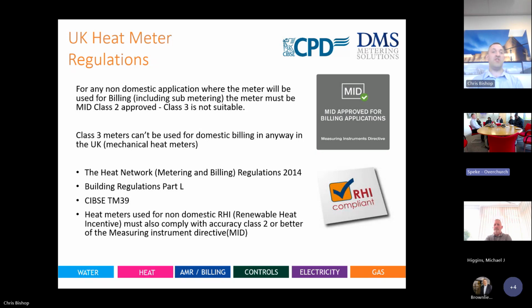Class 3 meters generally were always mechanical. So it was always moving parts. It was always reliant on the turbine, the spinning wheel, the pulsed output design. That became a thing of the past. So moving forward with regards to regulations, we still see Class 3 meters installed. They should no longer be installed.